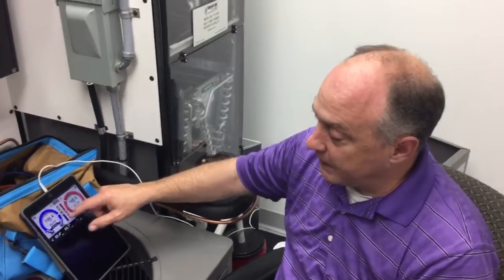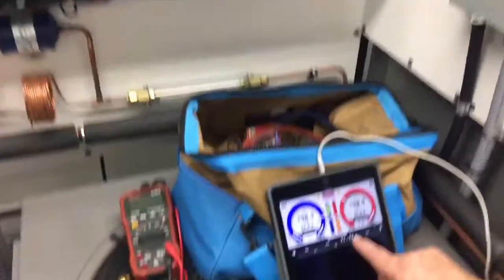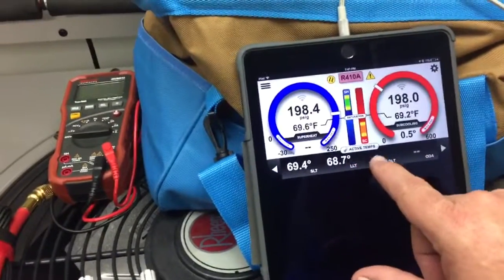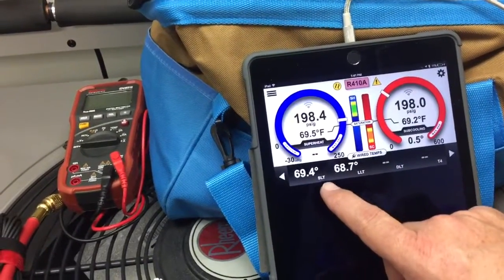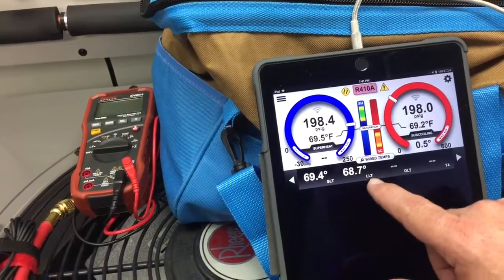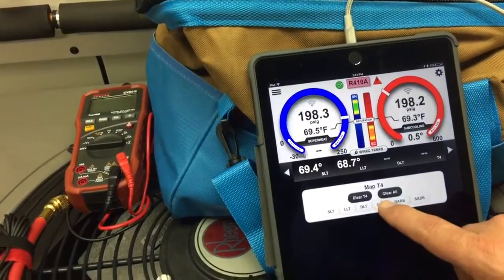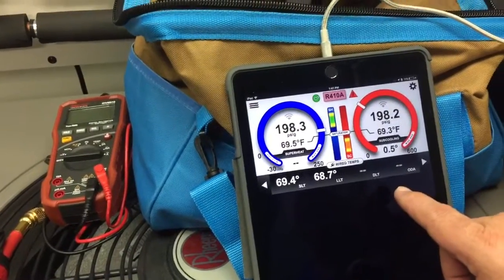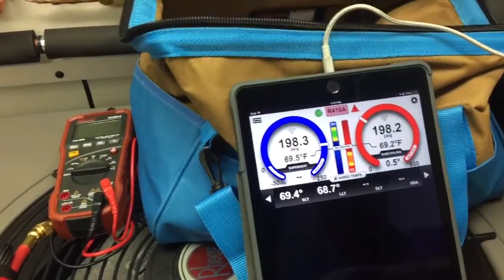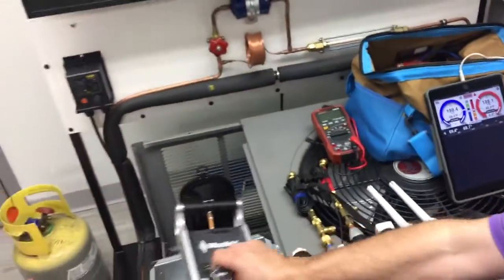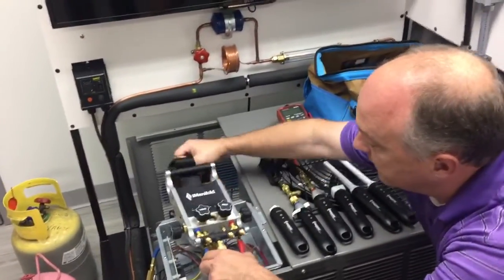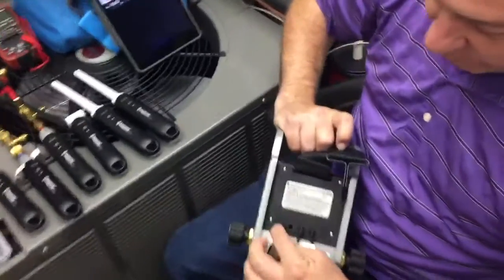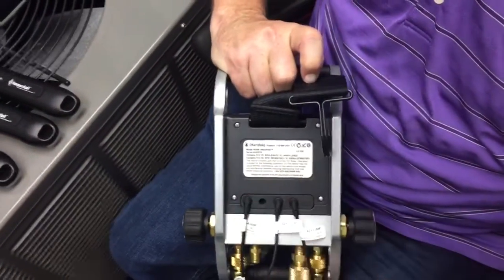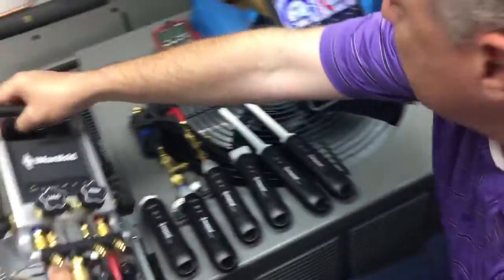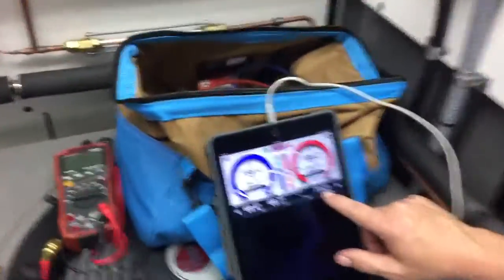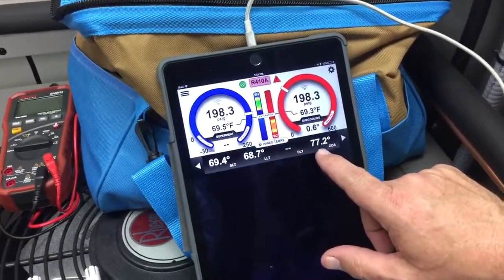Now one other piece of the mapping here, if we go back here, you'll see that we have two screens here. One is active temps and one is wired temps, and they're two different things. By default, this comes suction line, liquid line, discharge line, and this one normally would say outdoor air, but because I mapped the outdoor air sensor, I cleared the mapping to it. And that outdoor air sensor probe would go back in the back of the iManifold. So if I'm going to take this here, I might plug this into the T4, and typically I use this for my discharge line. And you can see here in just a second, that T4 now is reporting as my outdoor air temperature, so all that's done.